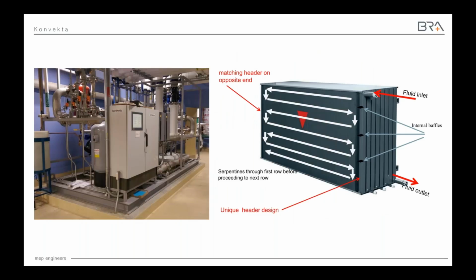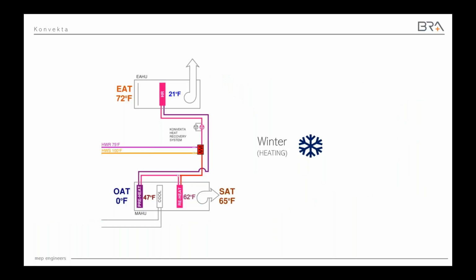This is a picture of our friendly heat recovery system from Konvekta. They have really advanced coils that can capture the exhaust air energy. And we're really taking that approach to the next level. So on the next slide, you can see on the top is the diagram of the exhaust air handler. On the bottom is the supply air handler bringing fresh air into the building. So you can see there's a heat recovery coil in the exhaust air handler in pink, and then there's a coil in the supply air handler down at the bottom that does the preheating of the outdoor air. Now, step one was to add a second coil to the supply air handler that does free reheat in the summertime, so it does wrap around the cooling coil.